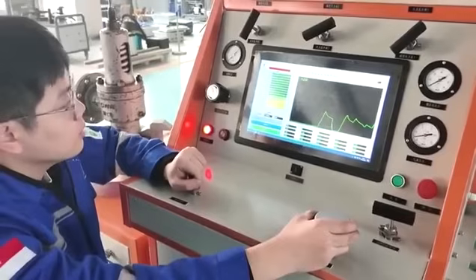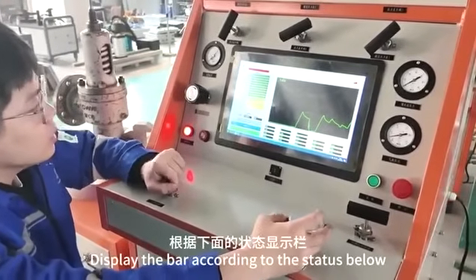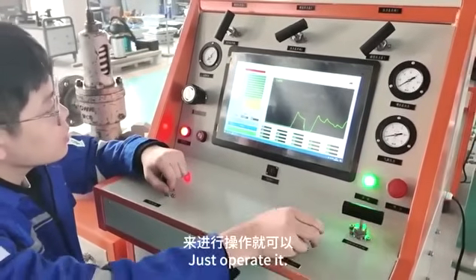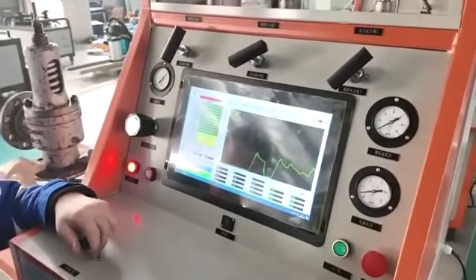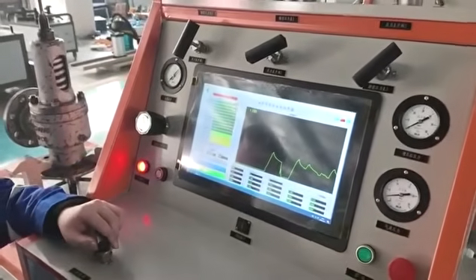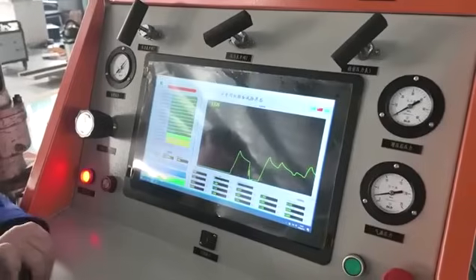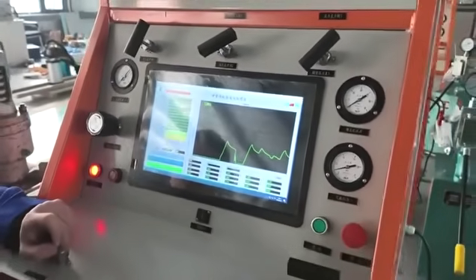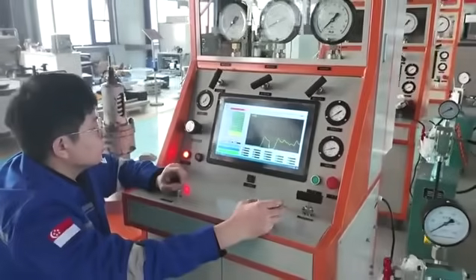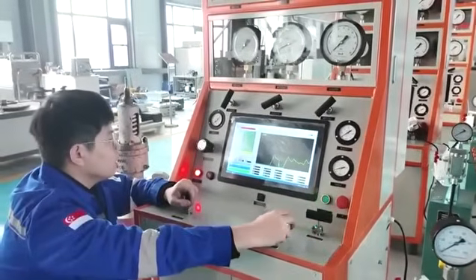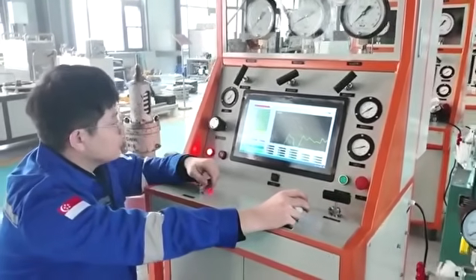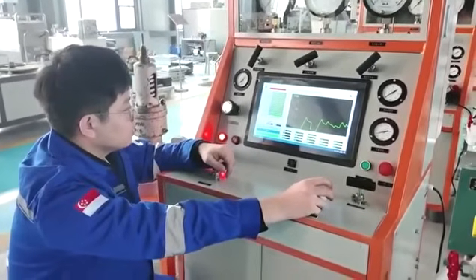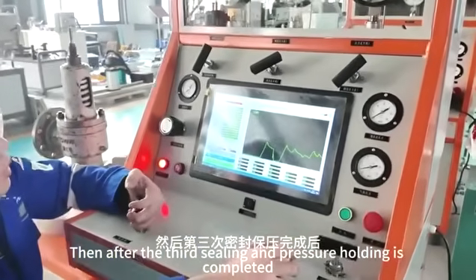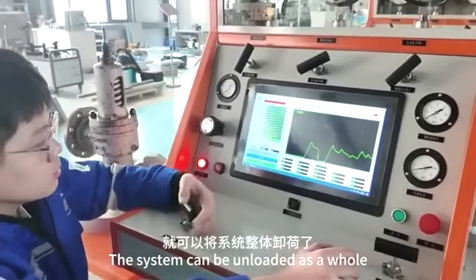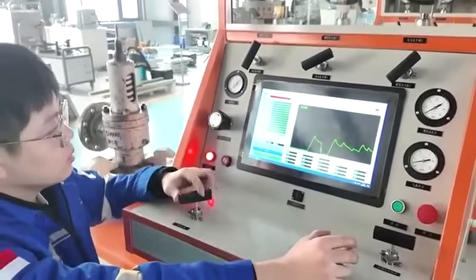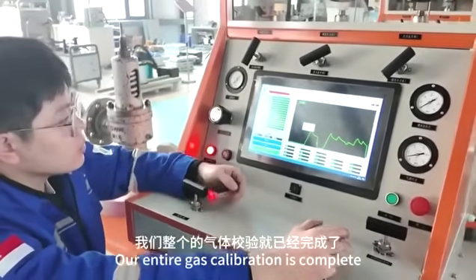And then the third time. His steps are the same 3 times. Display the bar according to the status below. Just operate it. Then after the third sealing and pressure holding is completed, the system can be unloaded as a whole. Okay, so our entire gas calibration is complete.